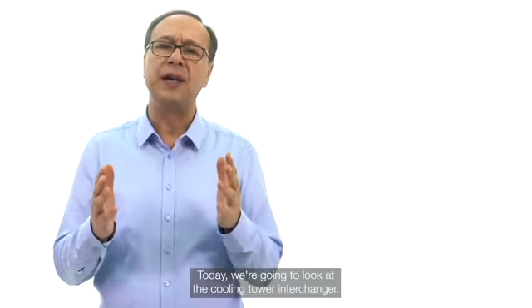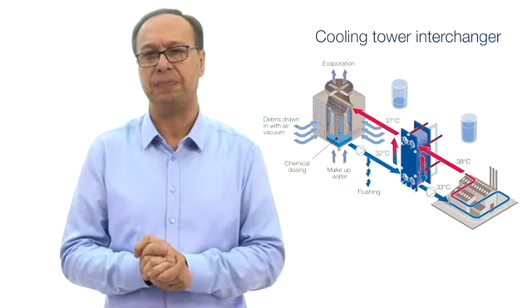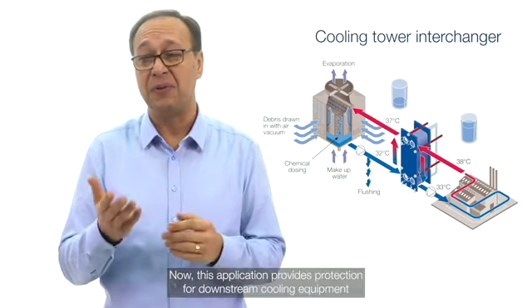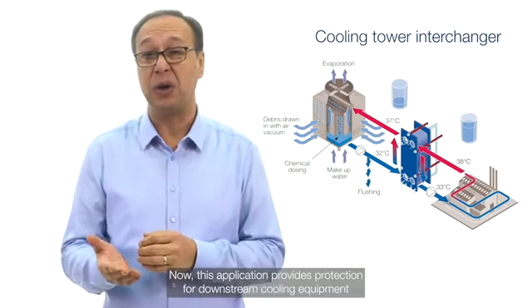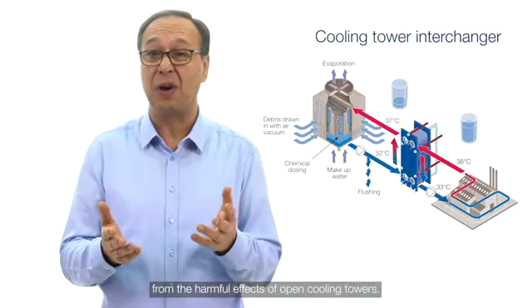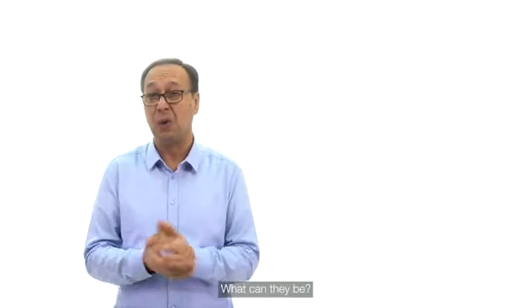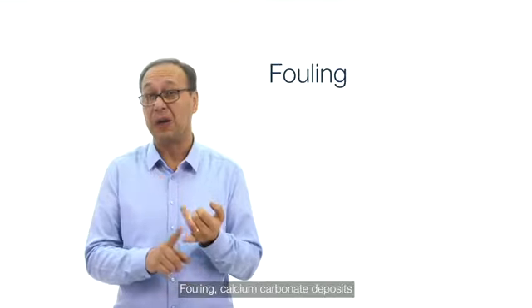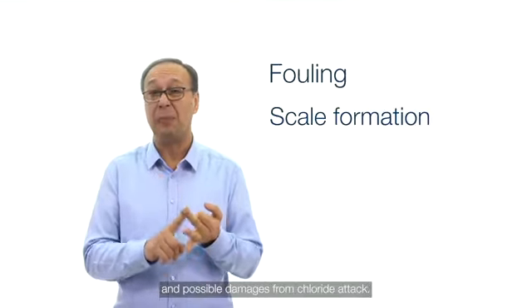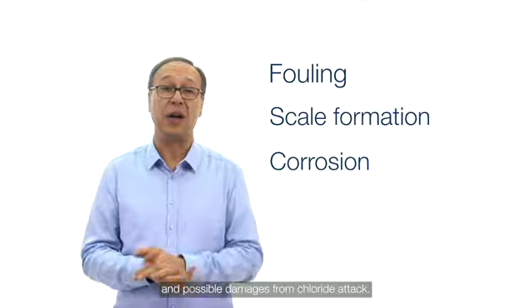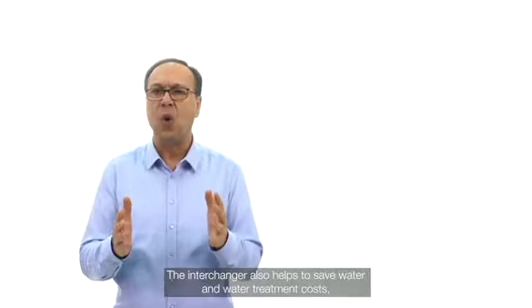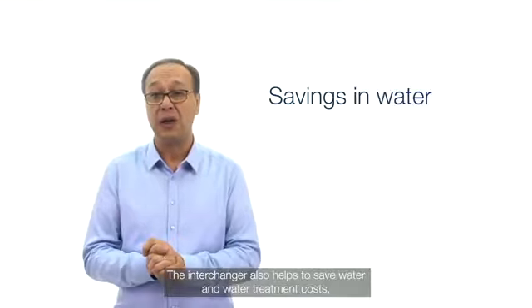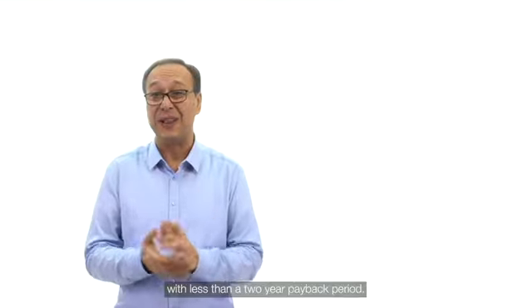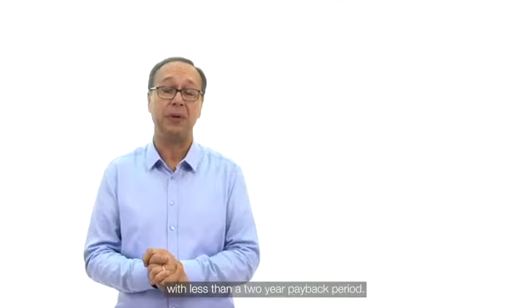Today we're going to look at the cooling tower interchanger. Now this application provides protection for downstream cooling equipment from the harmful effects of open cooling towers. What can they be? Fouling, calcium carbonate deposits, and possible damages from chloride attack. The interchanger also helps to save water and water treatment costs with less than a 2-year payback period.